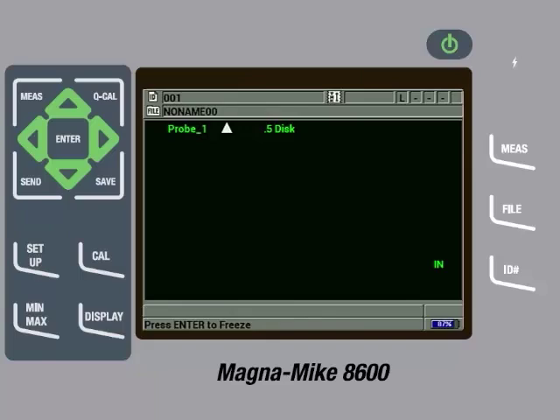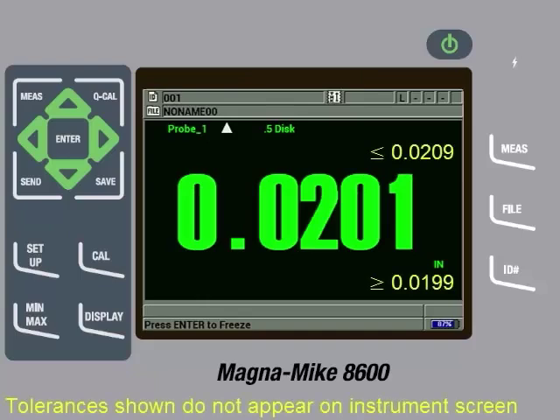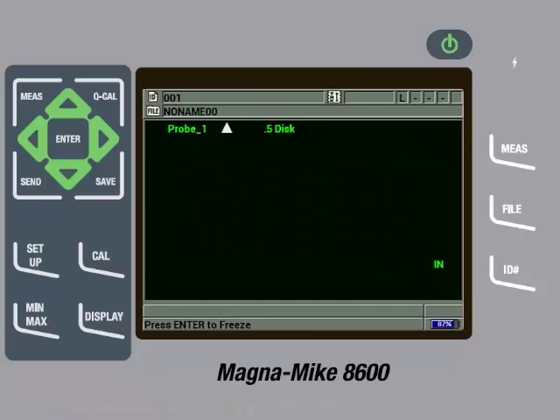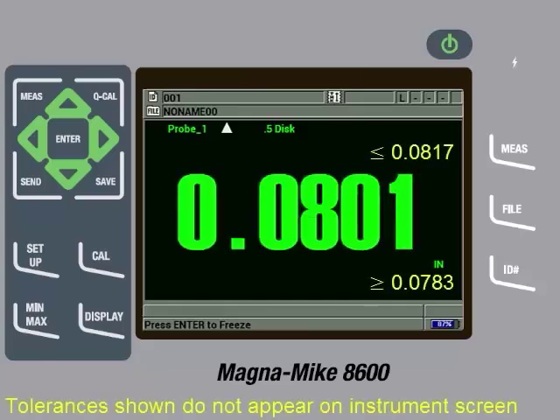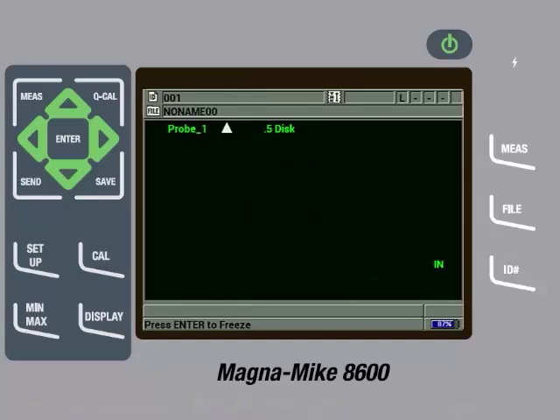If they are not, you can try removing the target from the probe tip and then pressing the Q-Cal key. We will check the 20 thousandths of an inch shim to make sure it is measuring within specifications, which it is. Then we will check the 80 thousandths of an inch shim to make sure it is measuring within specifications, which it is.